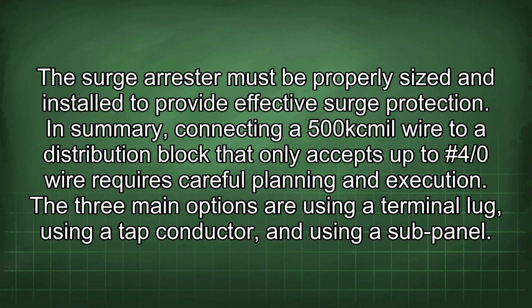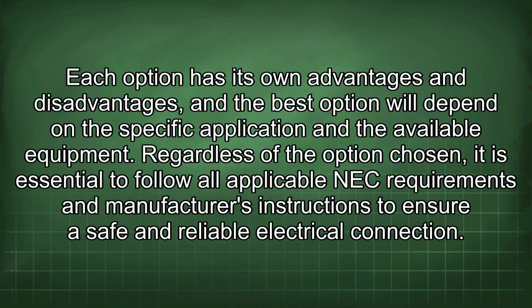In summary, connecting a 500 kcmil wire to a distribution block that only accepts up to #4/0 wire requires careful planning and execution. The three main options are using a terminal lug, using a tap conductor, and using a subpanel. Each option has its own advantages and disadvantages, and the best option will depend on the specific application and the available equipment. Regardless of the option chosen, it is essential to follow all applicable NEC requirements and manufacturer's instructions to ensure a safe and reliable electrical connection.